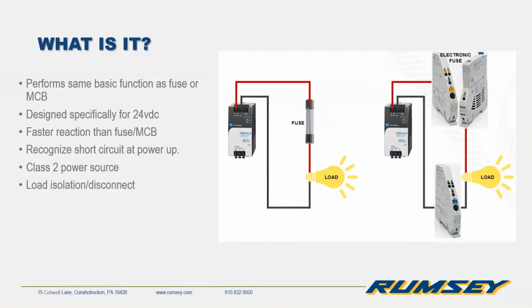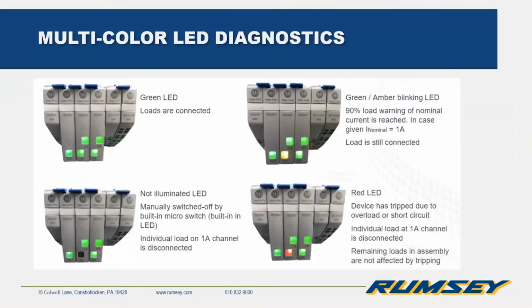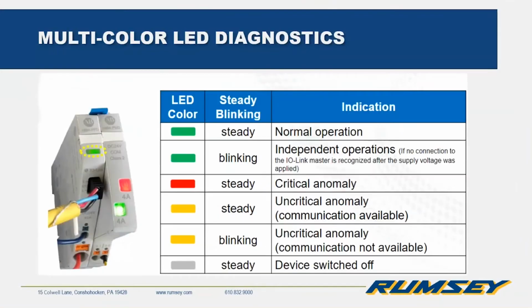Additionally, they have multicolor status indicators, allowing for fast diagnosis of problems. Here you see green, all the loads are connected, yellow for 90% load capacity, and red for disconnected or tripped loads. If you go to the next slide, it will show you that we also have the ability to connect these via IO-Link, and you can get that data out of the panel and feed it up to a PLC or an HMI, so you can get that visibility outside of the panel. You can set up alerts for when these trip. It's a cool new product that provides a new way to protect those 24-volt components versus traditional means.